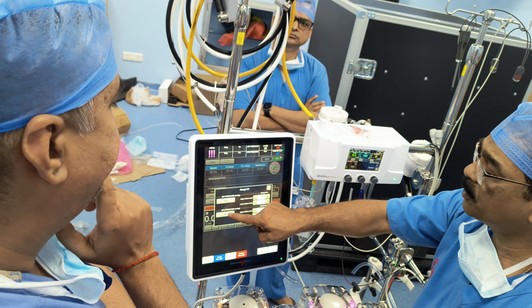Now you are circulating, recirculating, monitoring all your pressure. Also, when you connect your arterial pressure here, you will also get a dial pressure. That is the beauty of this. As soon as your aortic cannula is connected, which means it will sense a positive pressure, this will give you a swing, which will reflect the arterial swing in the cannula.